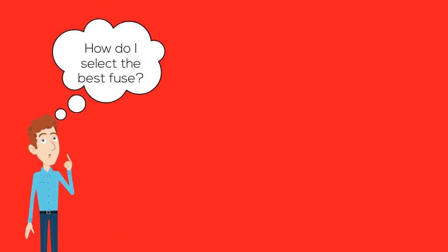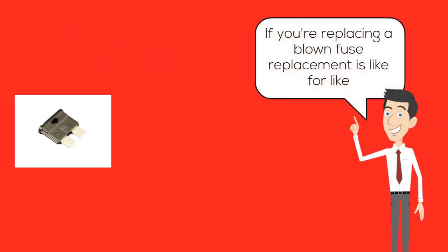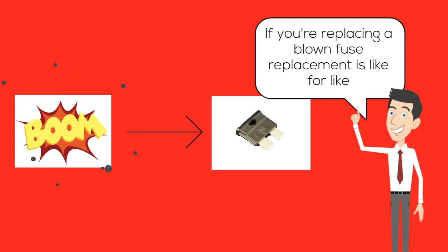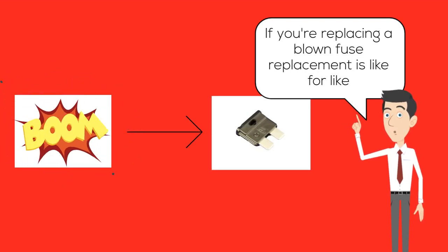So how do you select the best fuse for your needs? Well, if you are replacing a fuse, then always match like for like, i.e. 10 amps for a 10 amp. If the fuse blows again, there is a bigger issue you need to resolve. Never go up a fuse size as this can lead to further damage and possible electrical fires.